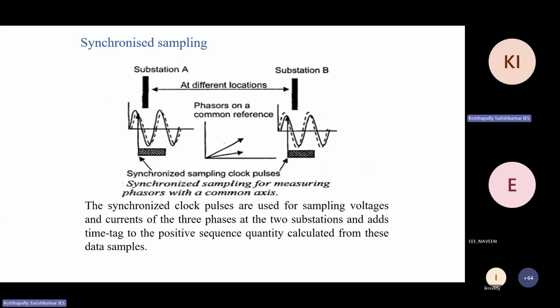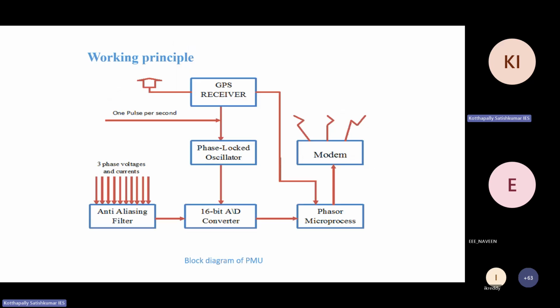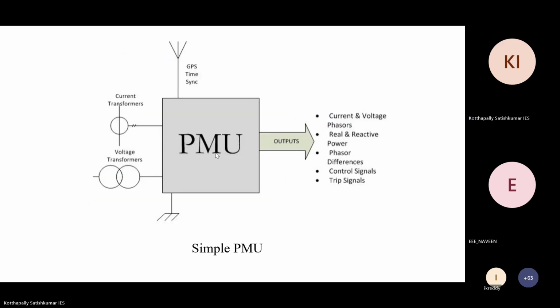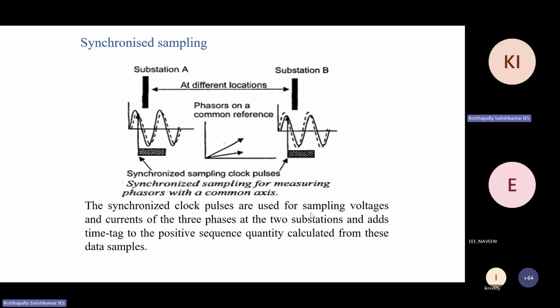Now, what is synchronizing sampling exactly? For example, there are two substations, A and B, at different locations, like 100 or 200 kilometers apart. You need a common reference for measuring this data. If you measure at the same time, you can compare the two voltages and tell what the angle difference is between substation A and substation B. The synchronized clock pulses we discussed are used for sampling voltages and currents of the three phases at the two substations, and adding a time tag. So whatever the PMU measures, it also adds a time tag.